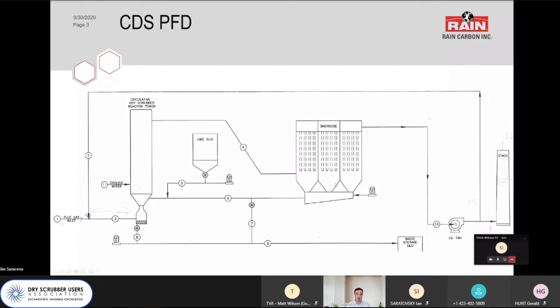There's two recirculations, so the spent lime that doesn't get sent to the spent lime silo goes back into the reaction tower. And the flue gas that is clean is recirculated back into the entrance of the reaction tower. Both of these recirculation loops improve reaction efficiency.